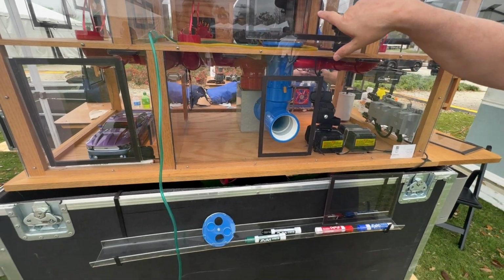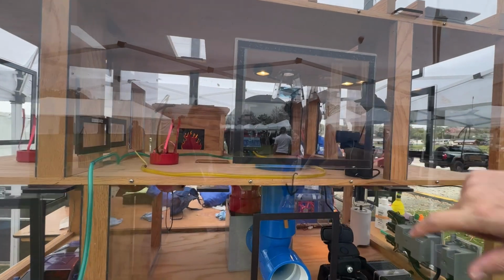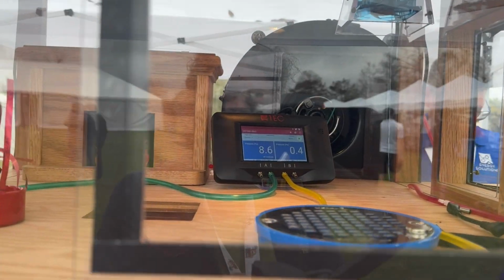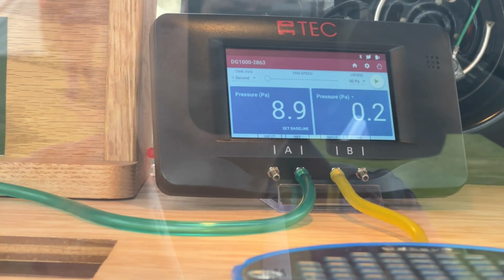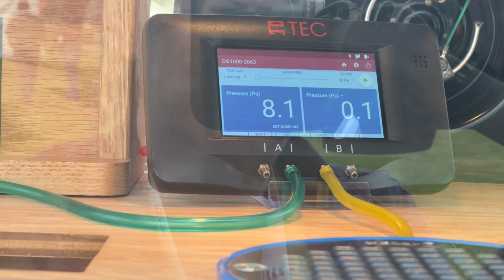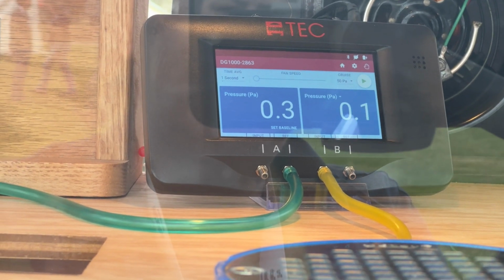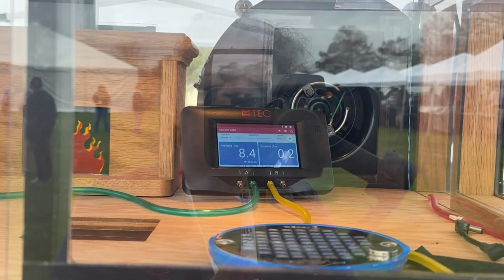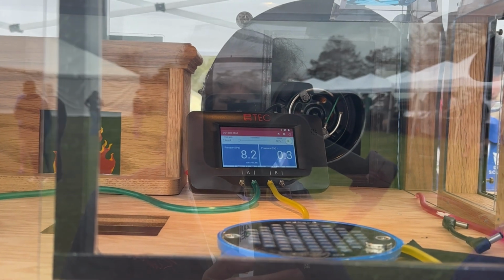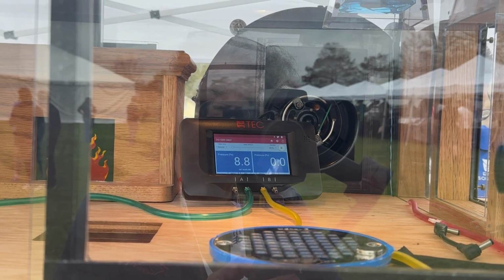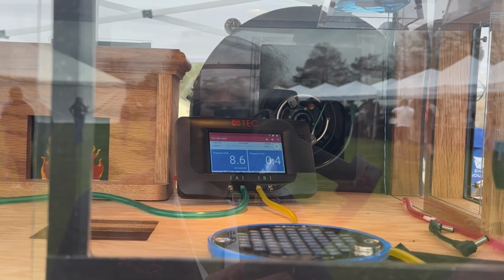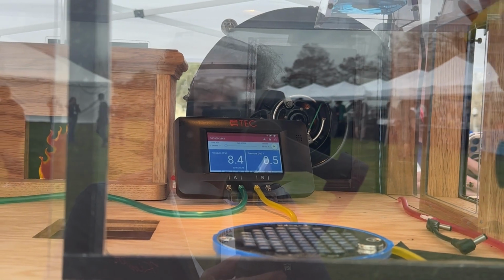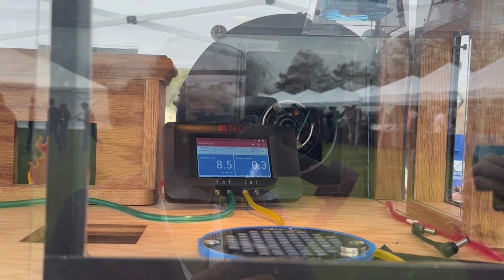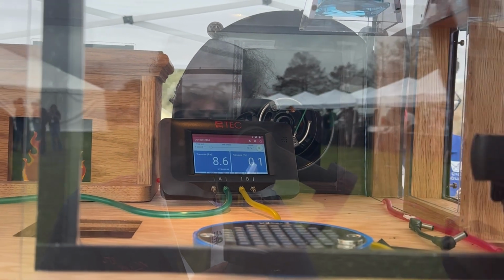But if you look at the pressure in the house, you see it's actually a positive number now. If I close the leak back, watch the number, it's going to balance out. Then I take it off, and it's unbalanced again. The reason it's positive now is because we've got all this air coming in, but not as much air coming out of the house, so it makes the house positive, pressurizing it. But that's what's going on in the house.